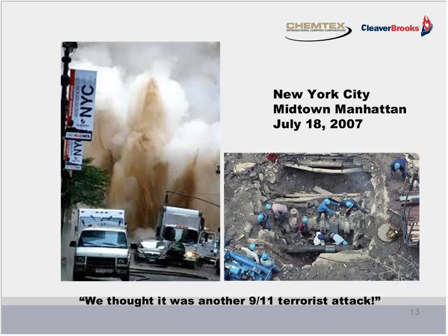And that's exactly what happened in New York City on July 18, 2007. Though it was a much greater slug of water than compared to a bowling ball, it was thousands of pounds of force hitting a weakened pipe section, which in turn ruptured, allowing hundreds of pounds of hot liquid to immediately flash into steam, blowing a huge crater in the Midtown Manhattan street, sending a tow truck about 20 feet in the air while scalding the driver over 80% of his body with 400-degree steam.